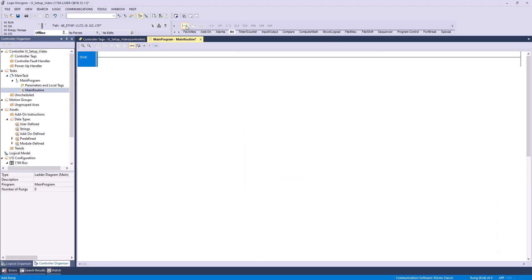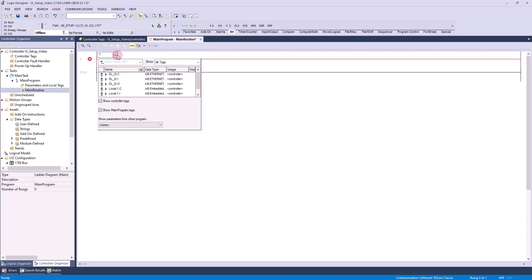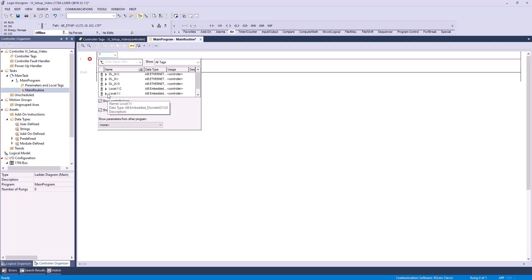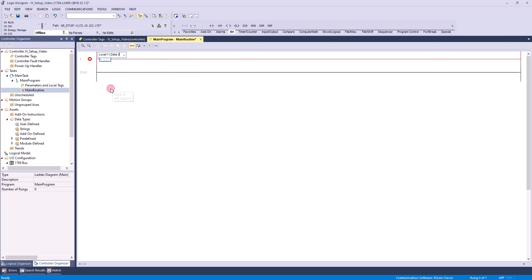We'll start by adding a rung. To do this, I'll double-click our rung icon. Next, I'll add a normally open contact by dragging this icon onto the rung. I'll double-click the question mark to define this contact as local input data 0, because I physically have a push button wired to input 0 on my PLC. You should choose whichever input bit you'll be using to trigger your iX for this element.